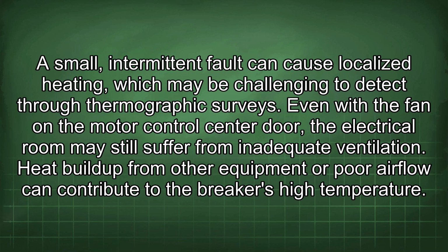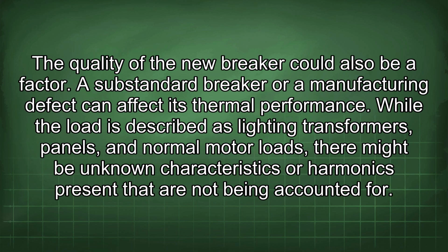Even with the fan on the motor control center door, the electrical room may still suffer from inadequate ventilation. Heat buildup from other equipment or poor airflow can contribute to the breaker's high temperature. The quality of the new breaker could also be a factor. A substandard breaker or a manufacturing defect can affect its thermal performance. While the load is described as lighting transformers, panels, and normal motor loads, there might be unknown characteristics or harmonics present that are not being accounted for.